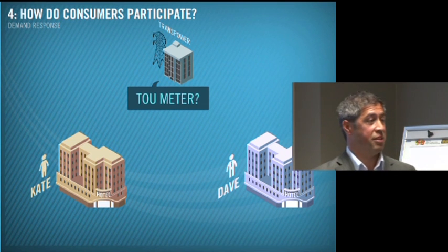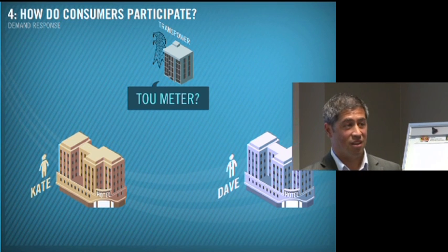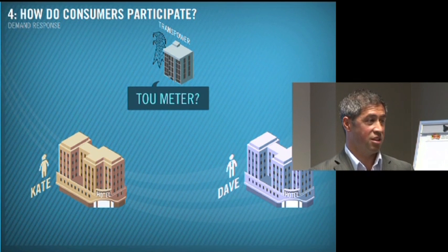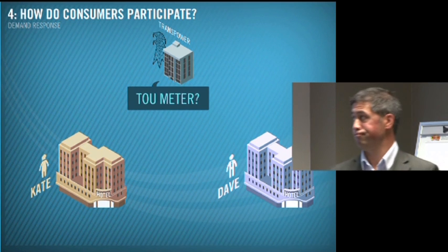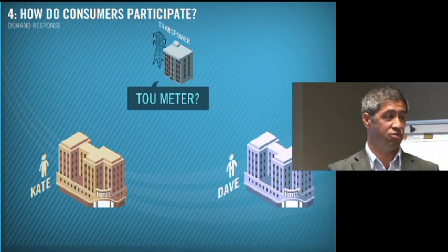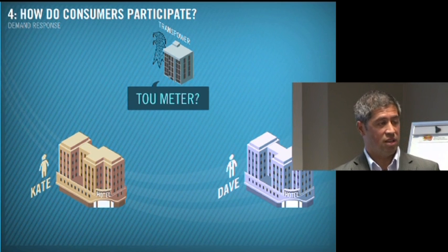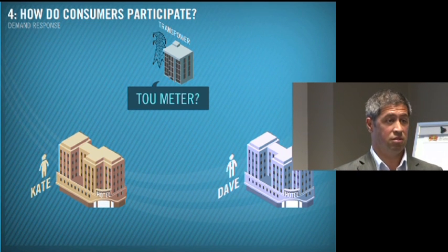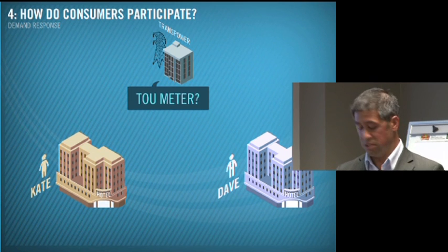Right, the next big thing is that one of the characteristics, I guess, of demand response is that consumers receive financial benefit. So they receive a payment. And in order to pay, we need to be able to measure their response. So at every single location that's participating, we're going to need to have a time of use meter or a half-hourly capable electricity meter. So that's the first thing.